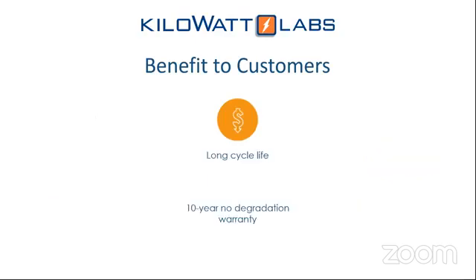Finally, the Sirius has a much longer cycle life. The supercap cells have a cycle life of 1 million cycles, but the infrastructure in the module, the electronics and so on, don't have a 1 million cycle life. That's why our warranty is for 10 years. But the key difference is that our warranty is a no-degradation warranty, meaning capacity on day one equals capacity at the end of 10 years. No chemical battery can offer this at the moment, because the electrolyte degrades with every cycle.